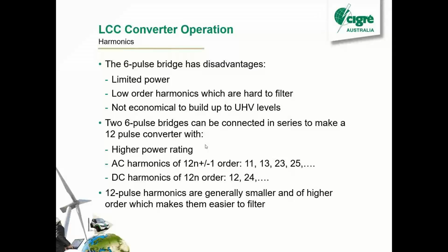So the 6-pulse bridge isn't great. You've got limited power within that topology, and you've got the low order harmonics, which are really hard to filter. So I'm talking the 5th and the 7th there. You need really big capacitors and reactors in the filter banks to hit those frequencies, which are expensive, and not that economical to build up to the really high voltage levels.